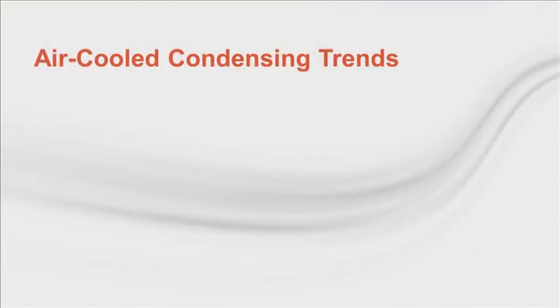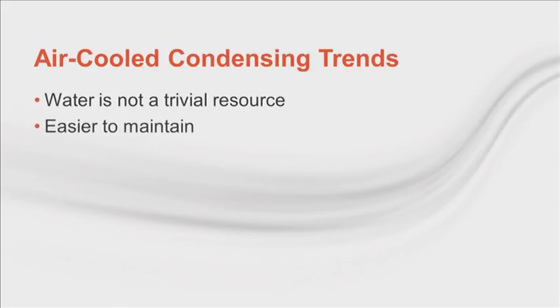This may be the age of the air-cooled chiller. That's because air-cooled condensers don't use water. This is not a trivial consideration. Air-cooled systems can be easier to maintain, however, they typically don't last as long as water-cooled systems do. Air-cooled systems don't carry water treatment costs and the chemicals because the chilled water system is a closed system, unlike the condenser water system.